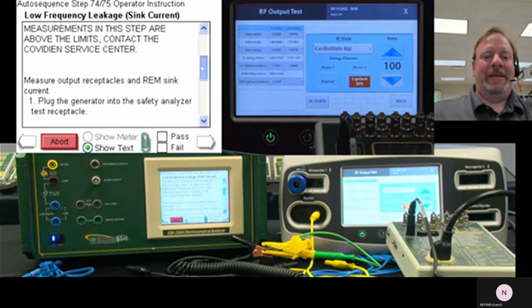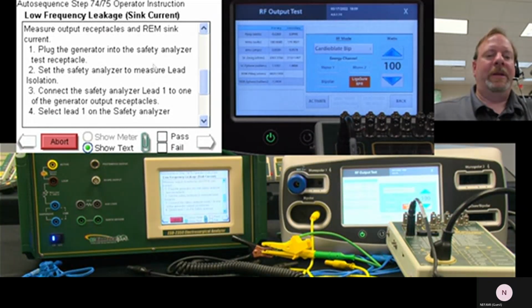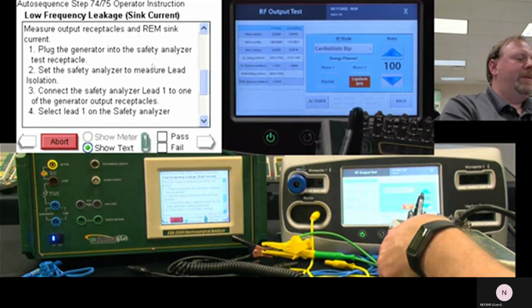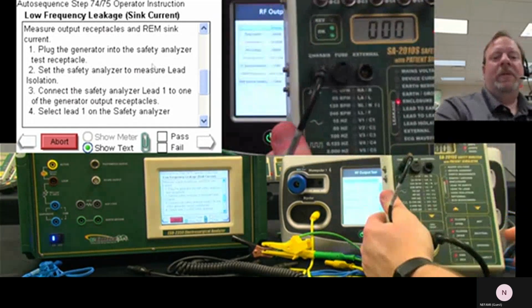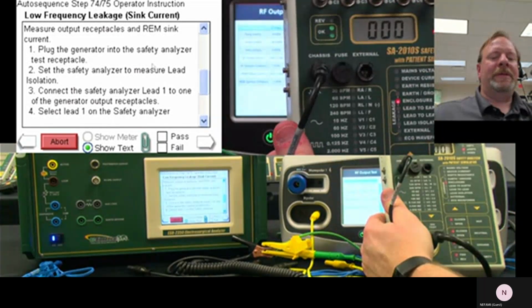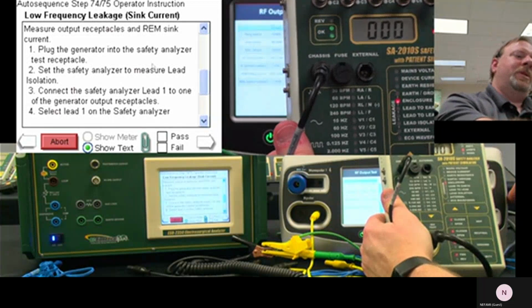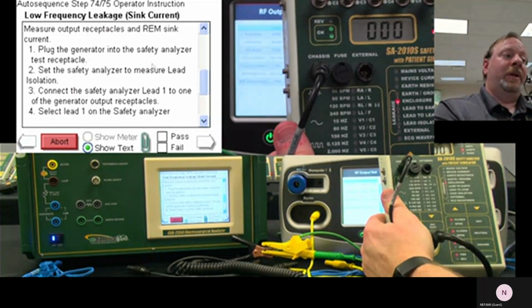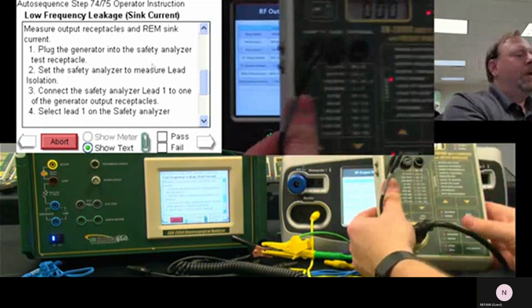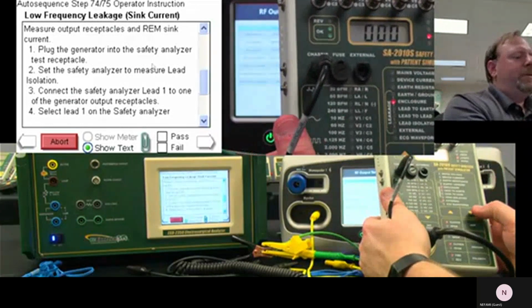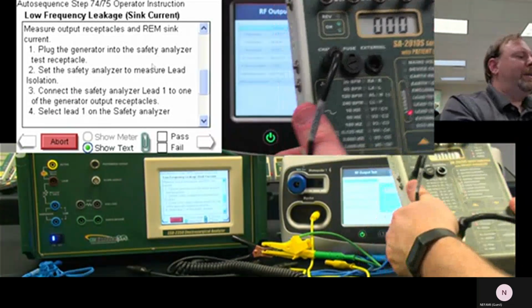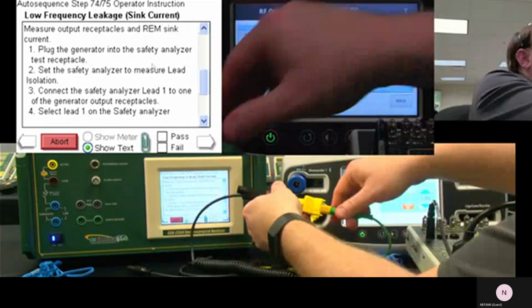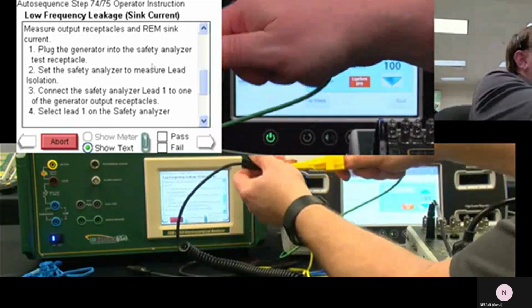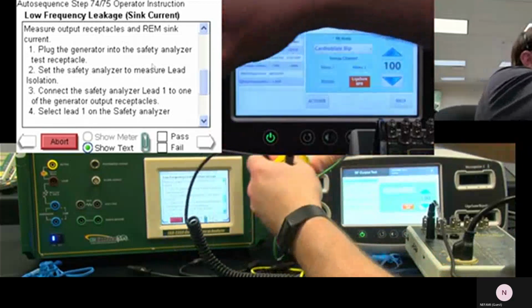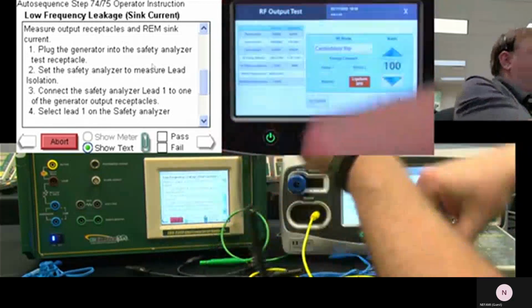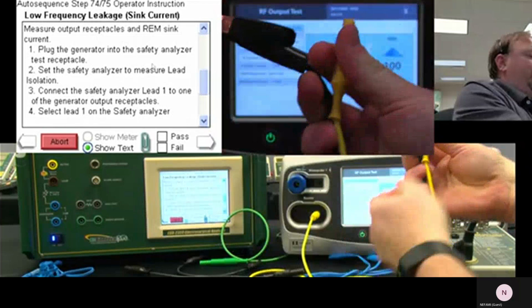The next to last step. I feel like I should slow down here a little bit because we're getting near the end and then it'll all be over. Okay, so the sink current. This is how much current can flow into the generator under a fault condition. So what we have to do is have a current source. In this case, we go to lead isolation, and I'll go back to my regular lead here. Get these guys to cooperate. I got a good tangle going.